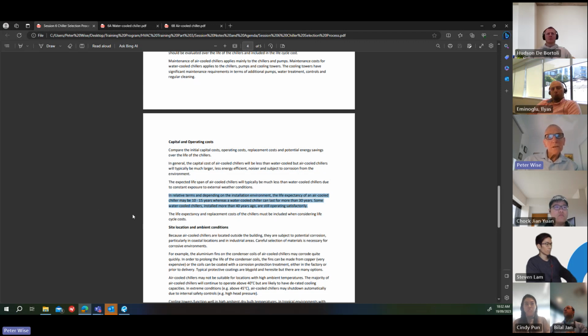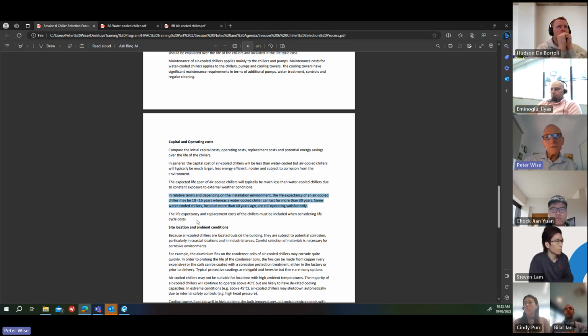So, water-cooled chillers will last longer because they're inside the building. They're built to last. Life expectancy and replacement costs of the chillers must be included when considering life cycle costs. So it's one thing to say to your client, an air-cooled chiller is your cheapest option. And if the client says to you, well, how much will it cost me over the next 20 years? Then you say, well, you may have to replace the air-cooled chillers in that time, but you probably won't need to replace the water-cooled chillers.